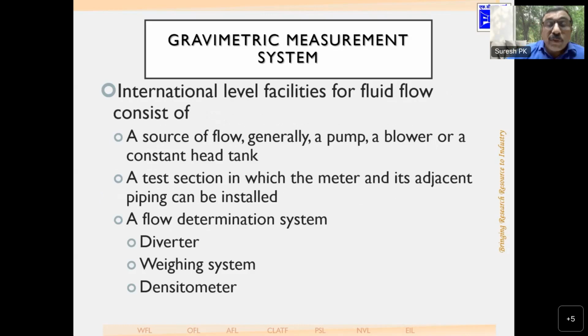International level facilities for fluid flow for gravimetric systems consist of a source of flow, generally a pump or maybe a blower for air, or a constant head tank, and a test section in which the meter and its adjacent piping can be installed, a flow determination system, that is a diverter, a weighing system, and a densitometer. You can pump the water directly into the flow meter under calibration and then make the measurement, or you can have a blower for air, or a constant head tank, which is supposed to be one of the best methods. A constant head tank is nothing but a tank inside a tank. The inside tank is always getting filled with water and supplies water for the calibration of the flow meter.